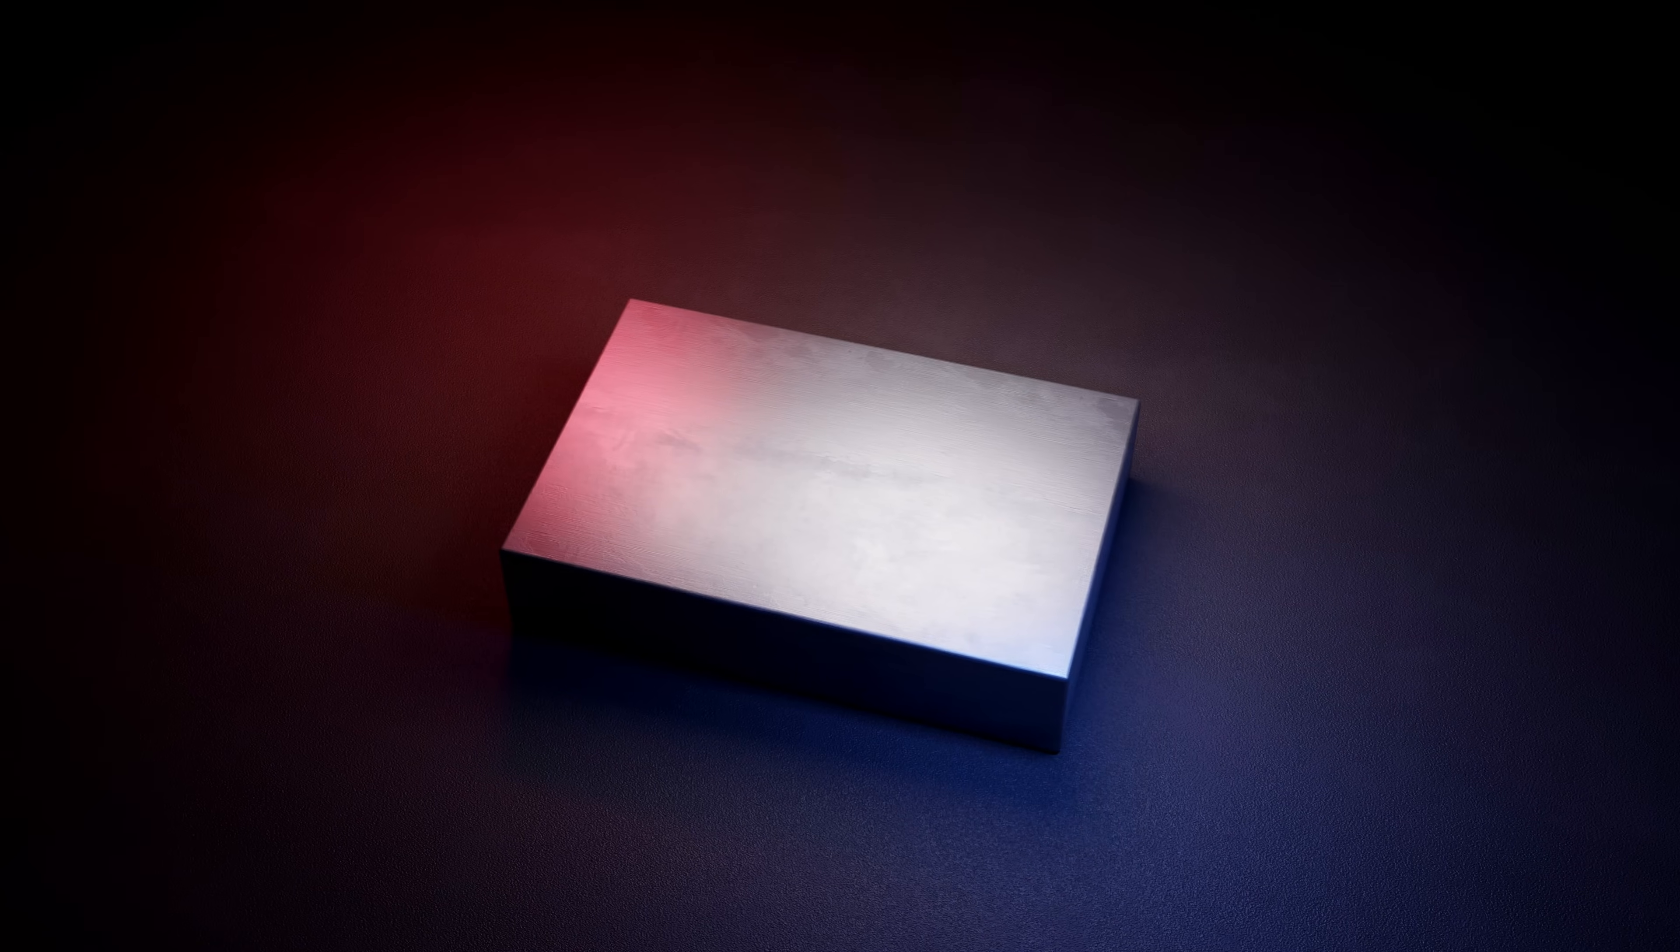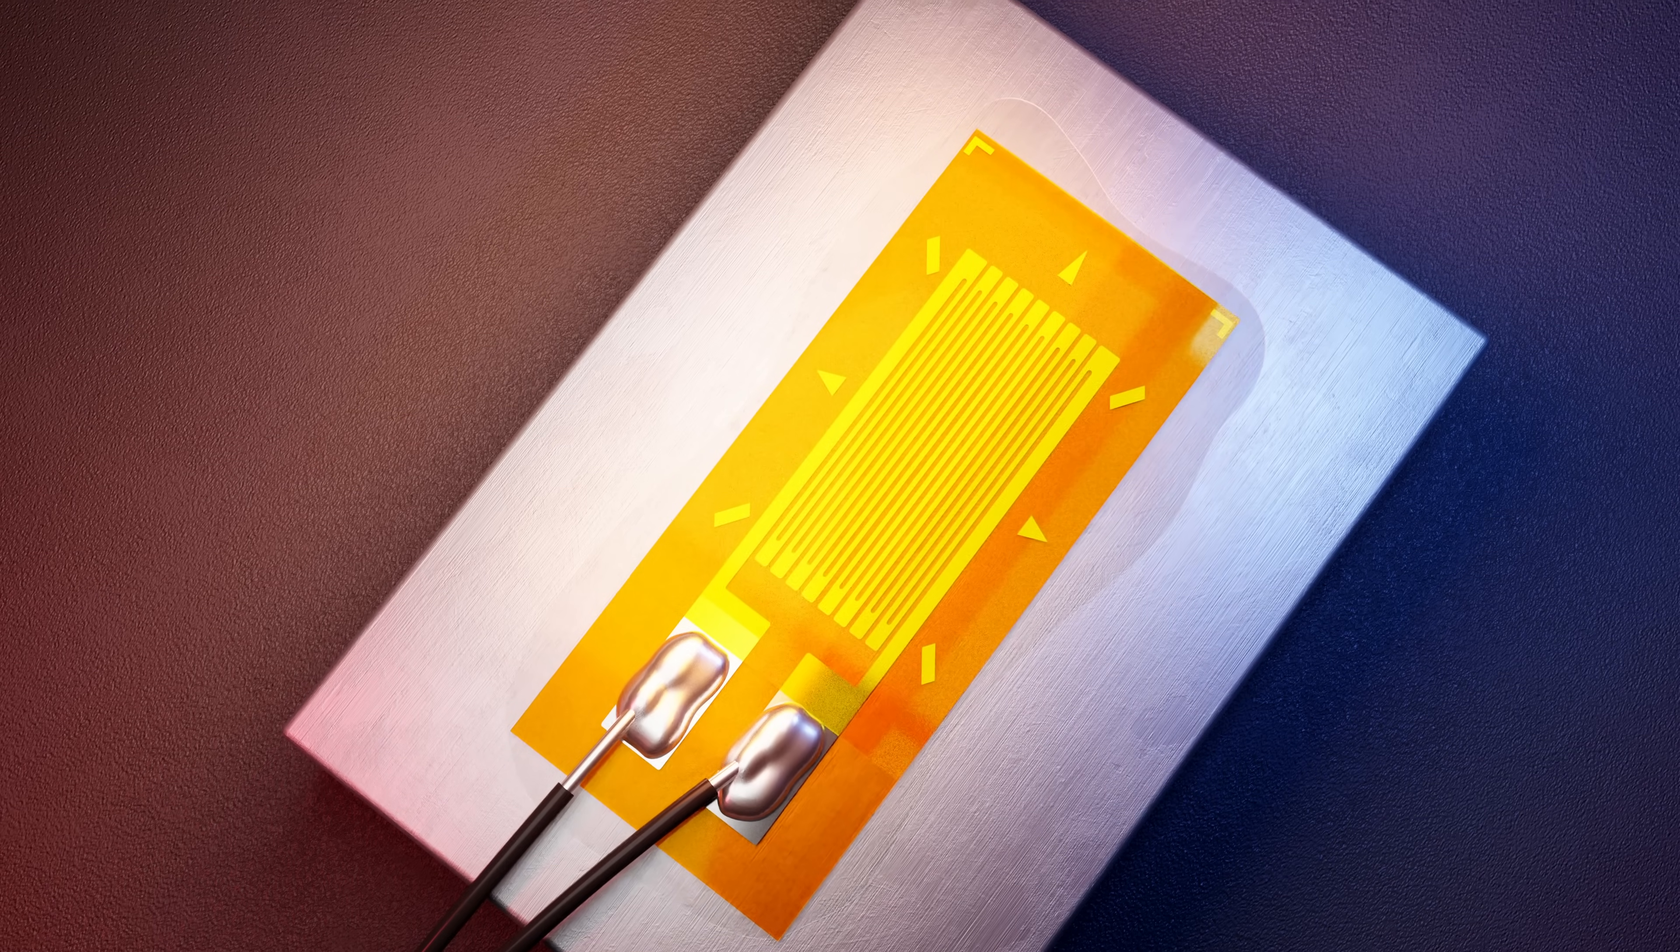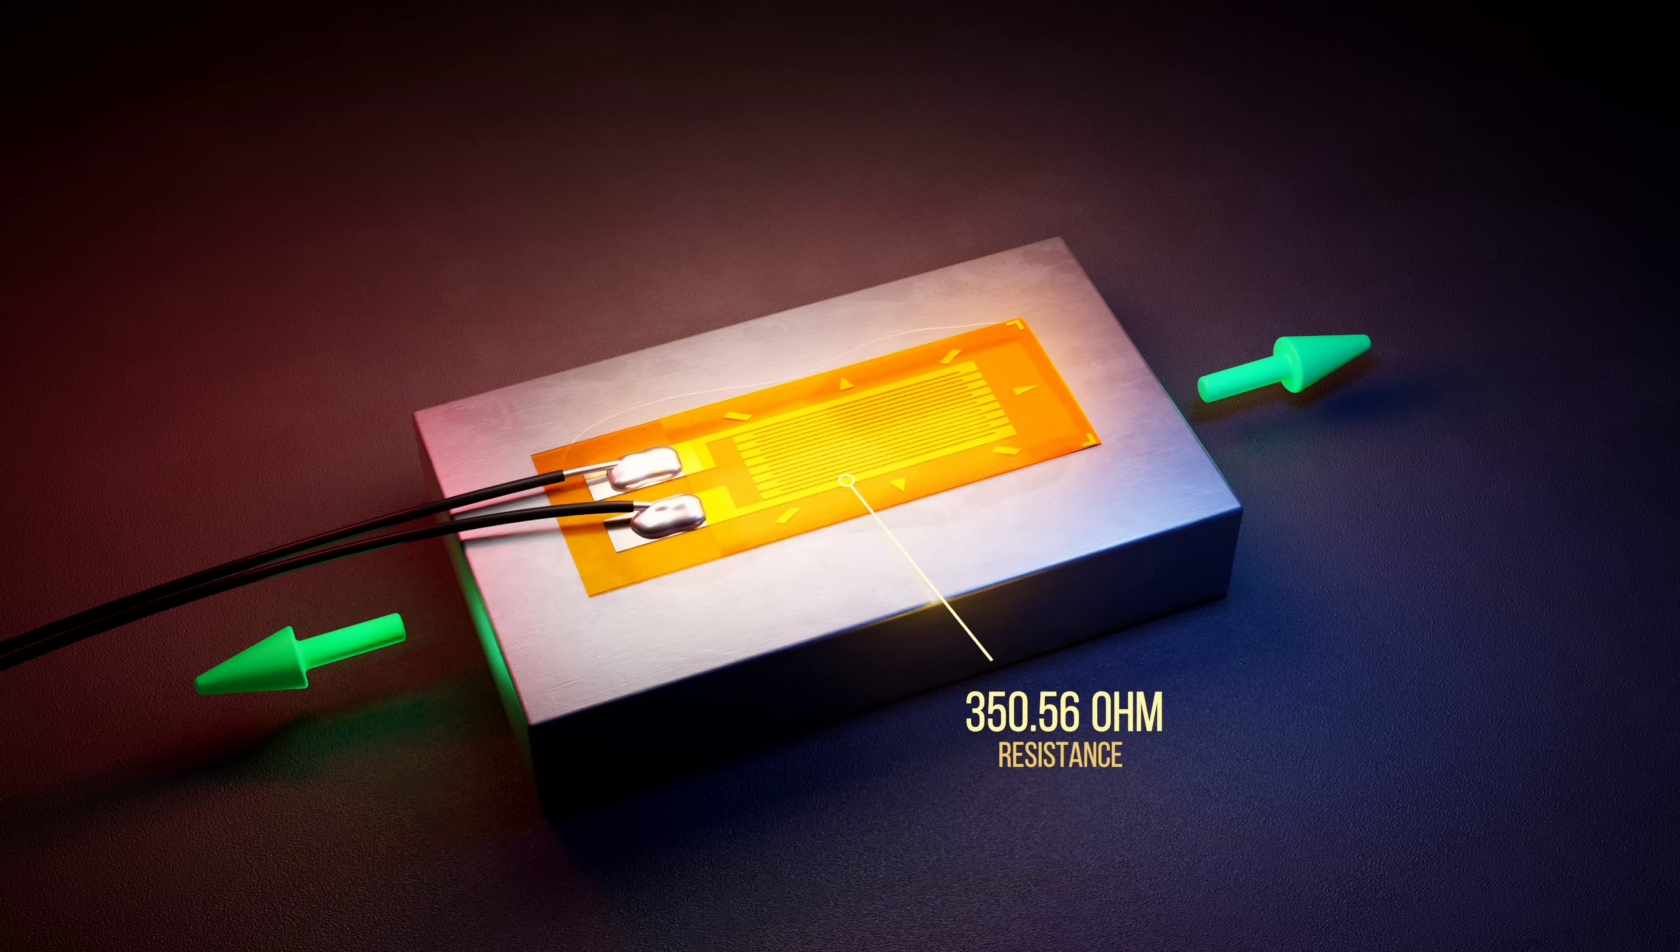These strain gauges are carefully bonded to the surface of the object being monitored, and work on the principle that the electrical resistance of a conductive material changes as it deforms. As the object stretches or compresses, the bonded strain gauge does the same. By measuring the change in electrical resistance across the gauge, we can accurately determine the object's change in length, and so the strain on its surface.